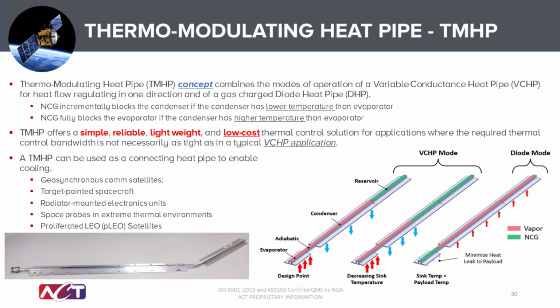Now, if for some reason, going to the third one, the temperature gradient of the pipe reverses, so for example, the sun hits the radiator, then the radiator heats up even more than the heat source is allowed to, then the non-condensable gas is swept by the vapor flow and changes location entirely into the pipe and blankets the evaporator, impeding entirely or almost entirely by design the heat access to the evaporator. So this is the thermomodulating heat pipe. The way it looks is on the left or the lower portion of this slide.